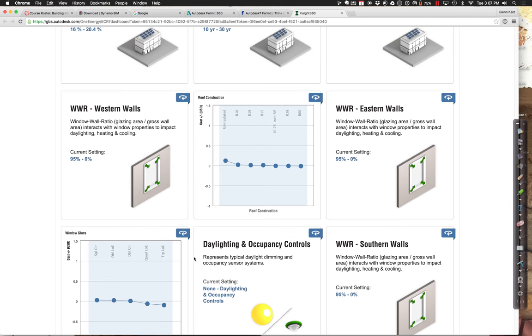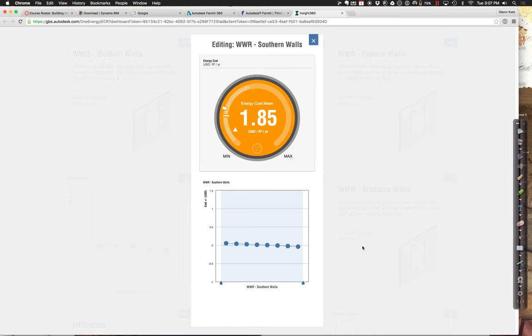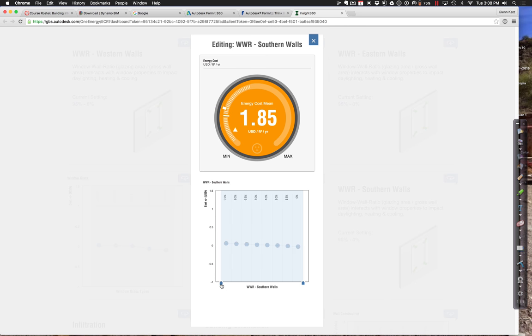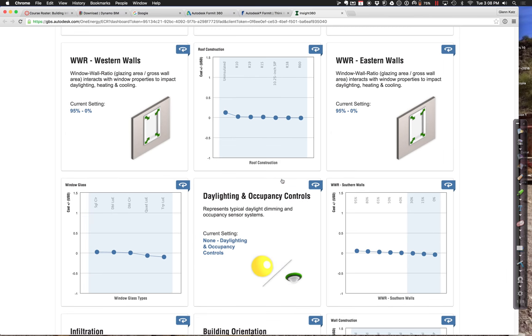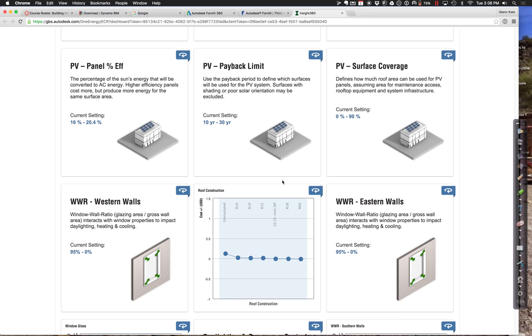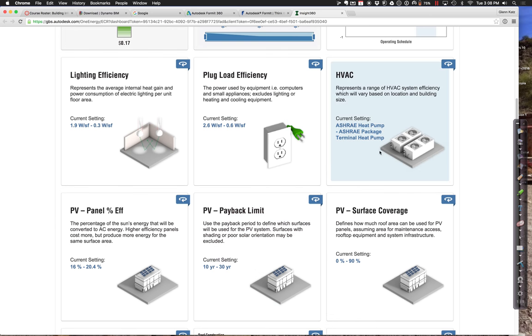Let's talk about the window-to-wall ratio for the southern walls. This might start having a little bit of a difference — anywhere from 95%, which is almost fully glazed, down to only 30% starts to have some small impact. The idea is to try and figure out what things are going to have the biggest payback for you.